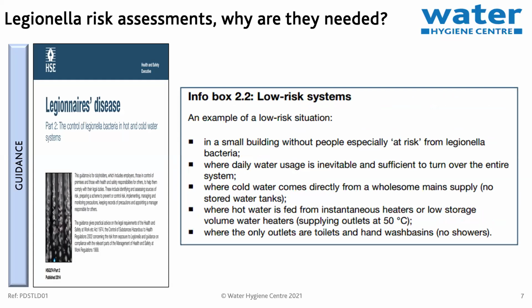And then we've got a slide about low risk systems and how to identify one. An example of a low risk system is in a small building without people especially at risk, where daily water usage is sufficient to turn over the entire system, where cold water comes directly from a wholesome main supply with no stored water tanks, and where hot water is fed from instantaneous heaters or low storage volume water heaters supplying outlets at 50 degrees C or greater, with the only outlets being toilets and hand wash basins and no showers. That's deemed a low risk system, granted, but it's still a risk system.